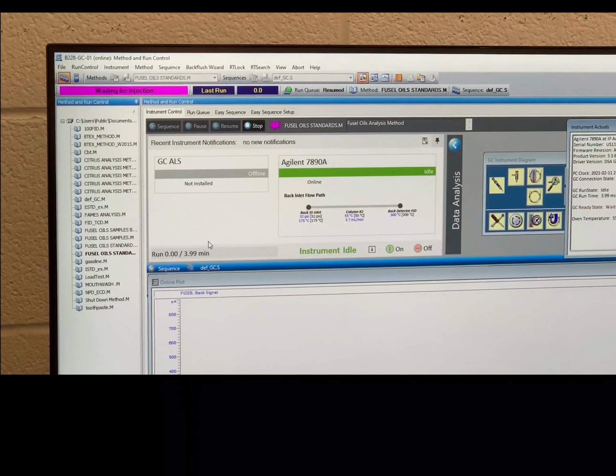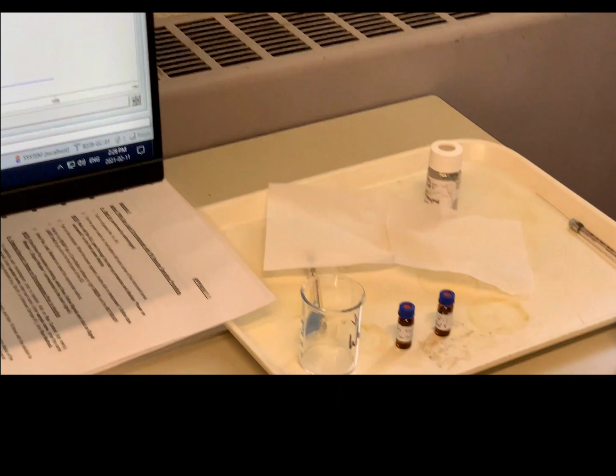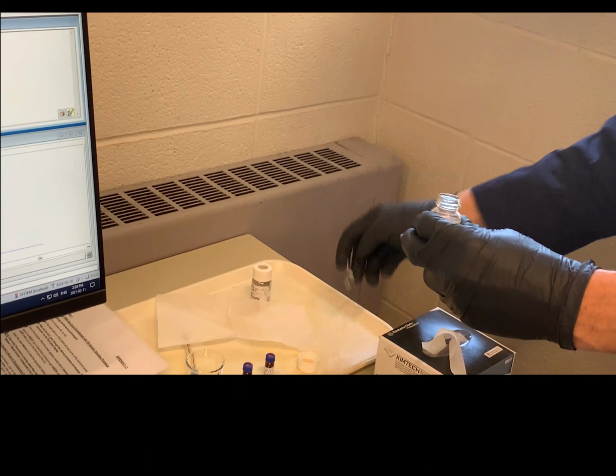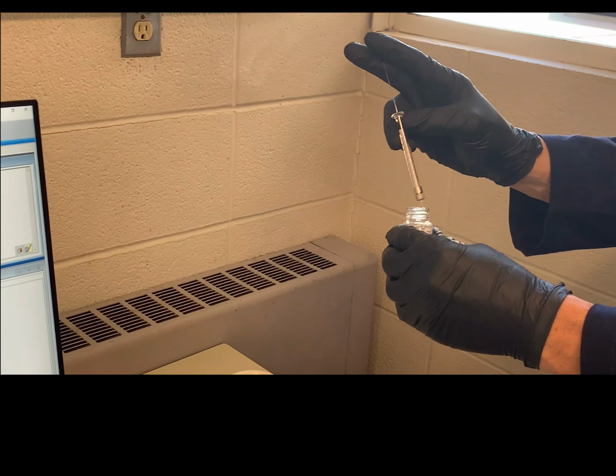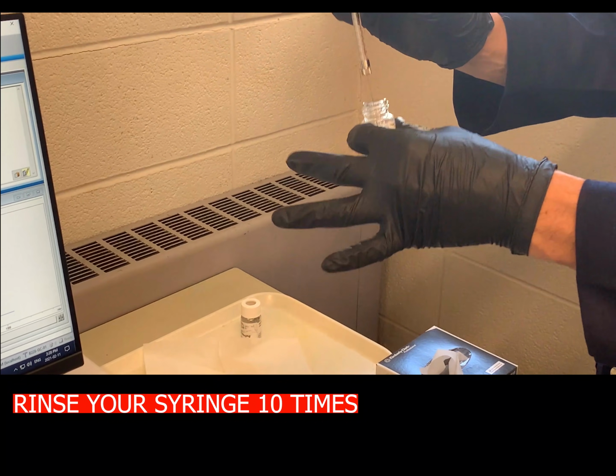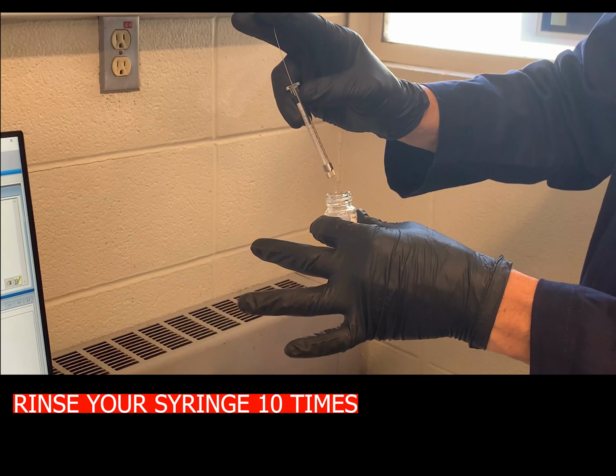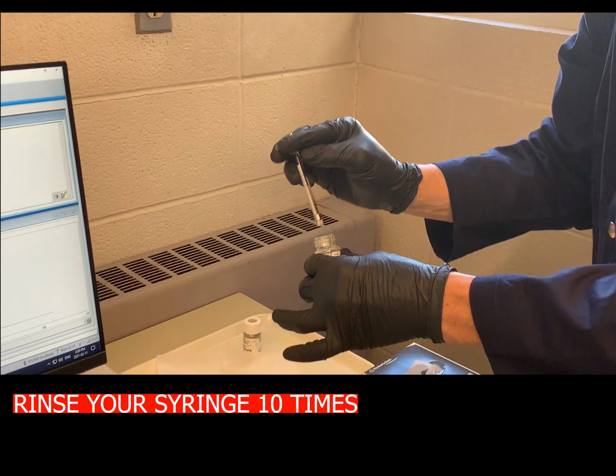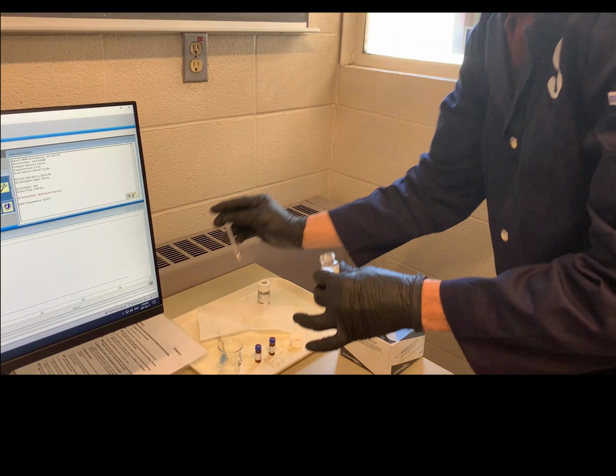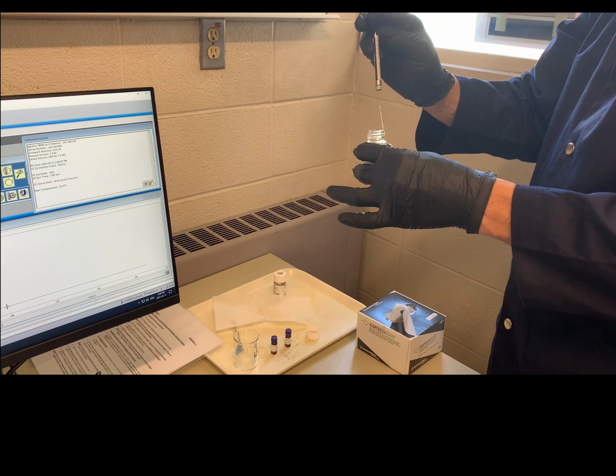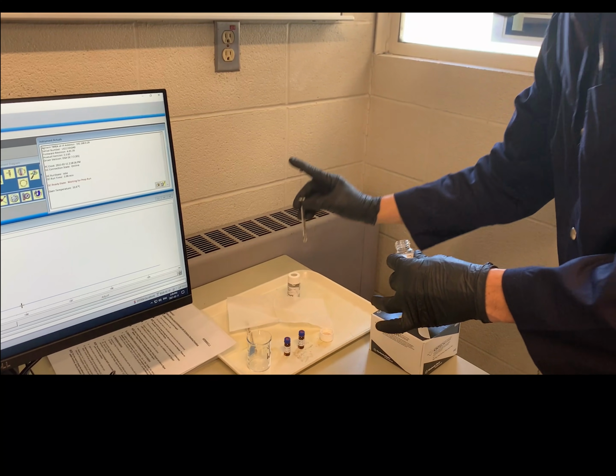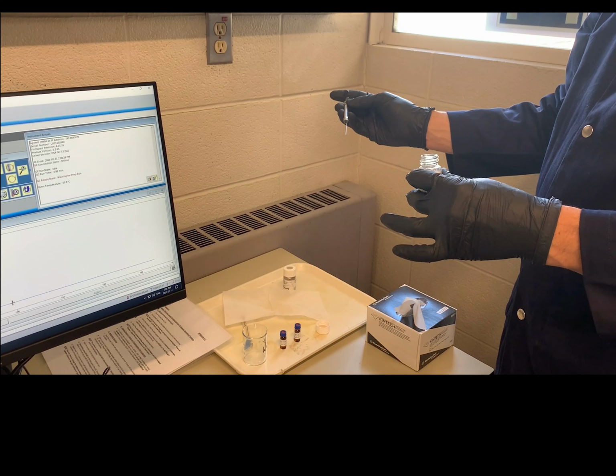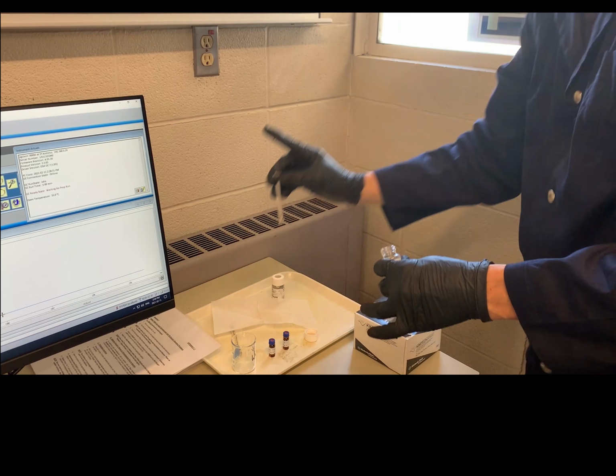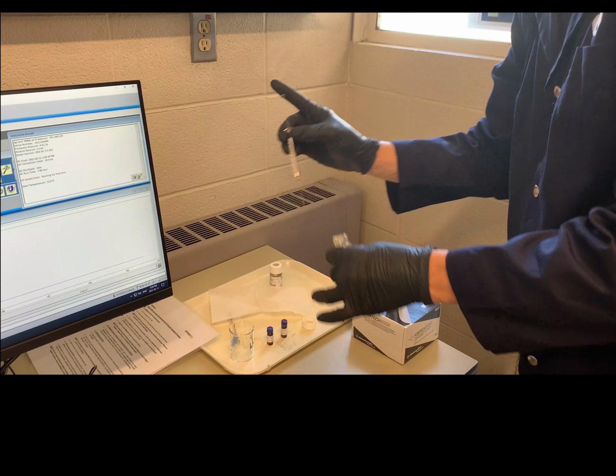So to do your injections, we will have all five standards sitting over here. You will have your diluent, and you are going to rinse your syringe 10 times with your diluent. Proper technique, just lift it up as I'm doing here with the two fingers, rinse it 10 times. One of the things you can do to make sure that the syringe is still working properly, when you are rinsing, just put a squirt onto the Kim wipe. Make sure that there's actually a wet spot forming and you know that the syringe is working properly.